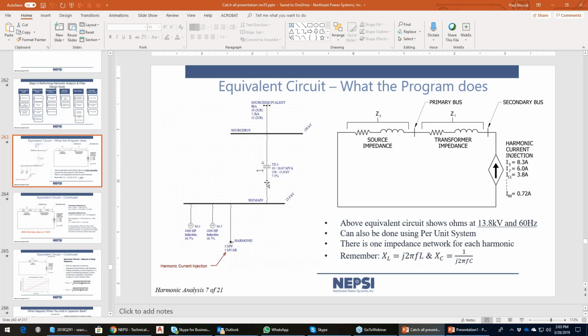The addition of impedance into the source is merely to change the short circuit level. You are going to decrease the short circuit level if you add impedance. By decreasing the short circuit level, you will change the resonant point. If you're adding capacitors, you're going to push your resonant point to a lower frequency. So that would be, of course, a concern.